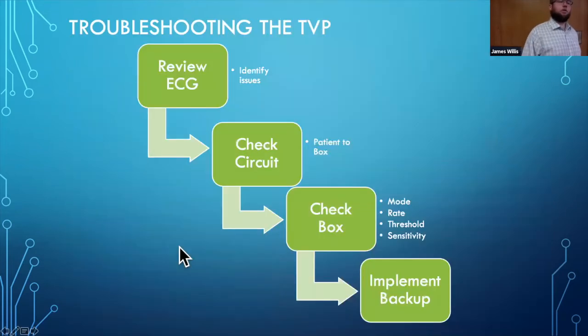All right, so troubleshooting the TVP. This is a really important piece. You've got to have a systematic approach, just like anything else we do in EM. Have a system that way when stuff is hitting the fan, you can kind of fall back on that. So the first thing is review the ECG and try to identify what's going on. Then you're going to check the circuit. You start at the patient and you work your way backwards to the box. Always start that way. If something happened to the device, that way you can find out very quickly.